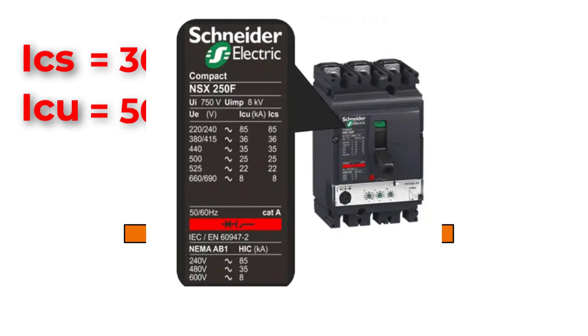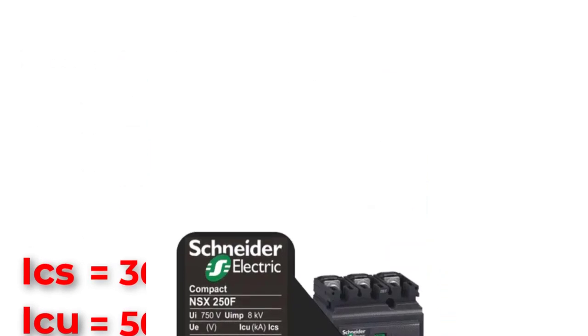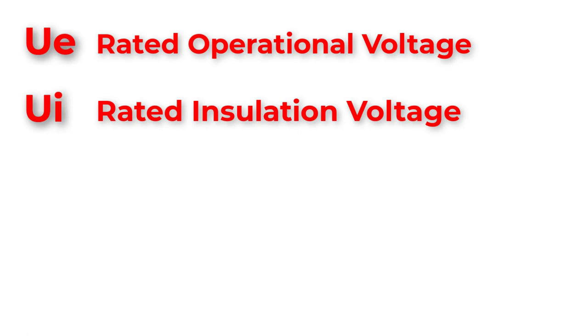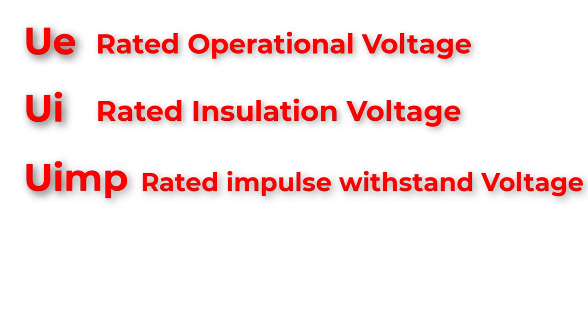On any MCCB nameplate, you will find the value of ICU in kilo-amperes at every operating voltage, and the value of ICS will be a percentage of ICU — it could be 60%, 80%, or 100%. Another important terminology is the rated operational voltage (Ue), rated insulation voltage (Ui), and impulse withstand voltage (Uimp).